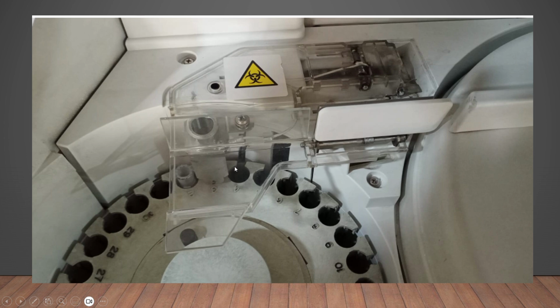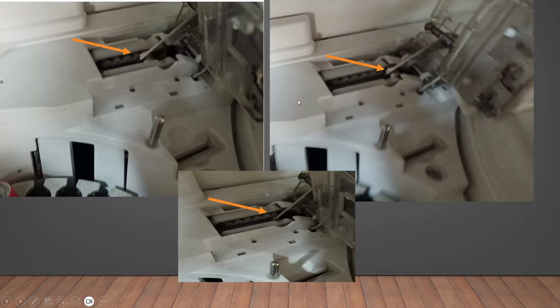The important thing about this instrument is that it works under an electrochemiluminescence assay. So there is an electrical enhancement that is present. Because of that, it has to make sure that there is no static electricity being conducted by the probe to the instrument. So because of that reason, it has got a cover. Now this cover, as you can see, has got a metal guard, and this metal guard is attached to this particular wire. This metal guard will make sure that the earthing of this static electricity happens when the sample is being picked up. Okay, so this can be opened up and down like this.